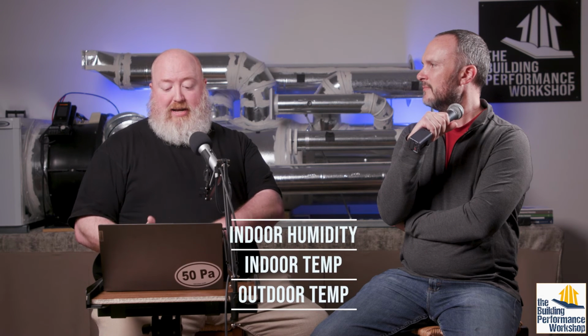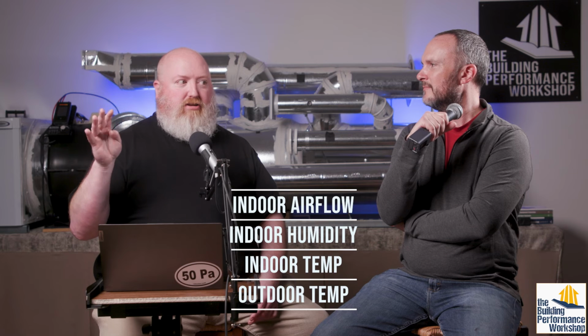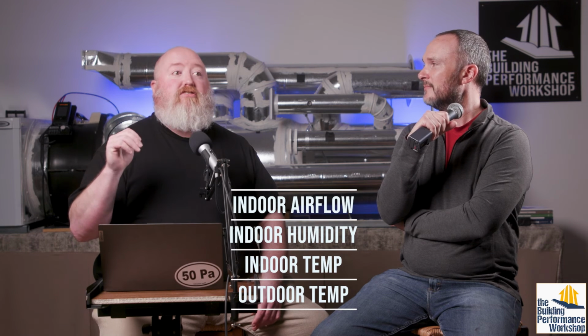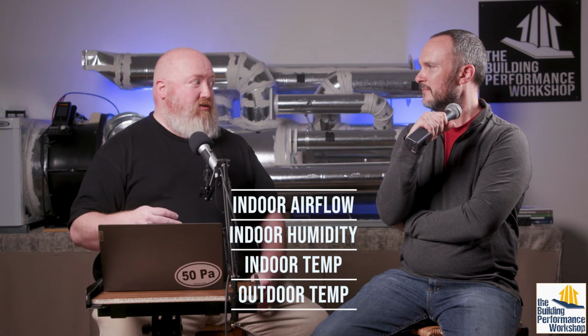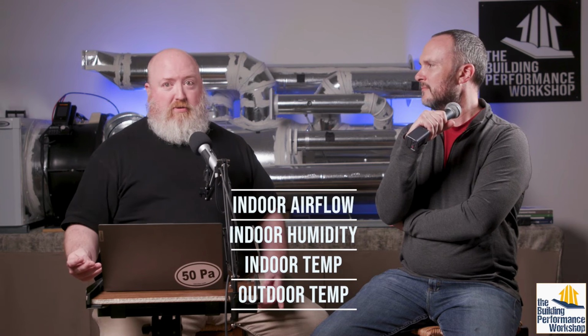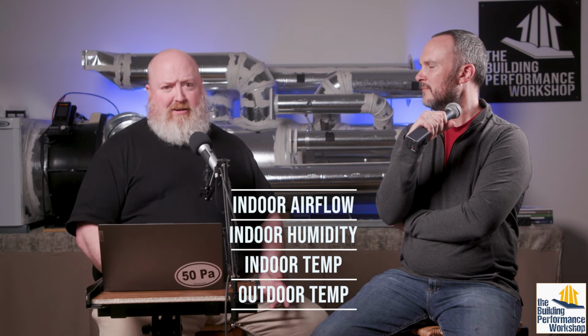So I know I'm here and I know I'm here, and I know I'm halfway between, so I can figure out where halfway between is. The thing is, when you figure out how much interpolation you need, you have an outdoor temperature, an indoor humidity, and a CFM - that turns into 32 data points. It's a good thing they have calculators, because doing it by hand, or even with the speed sheets from ACCA, can be a pain.